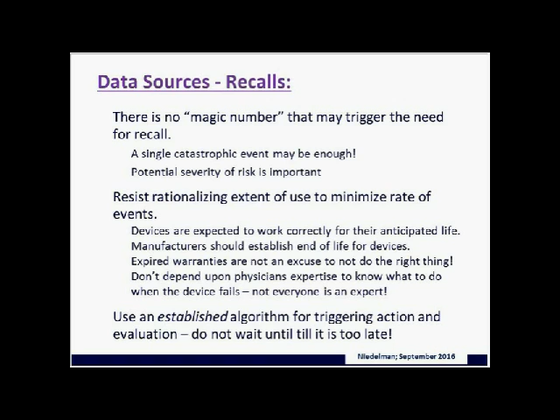The important thing is, in anticipation of a recall, you should have an established algorithm within your own firm for triggering that action. Don't wait until it's too late. Make sure that you have this all well baked before the situation arises. When we talk about end of life for devices, what the agency considers end of life is you will not service the device anymore. You will not make parts available for the device anymore. And any continued use of the device is not at your risk, but at the user's risk going forward, and you have provided notification to the user that end of life will occur within a certain period of time, so they have opportunity to make changes and update their device going forward.